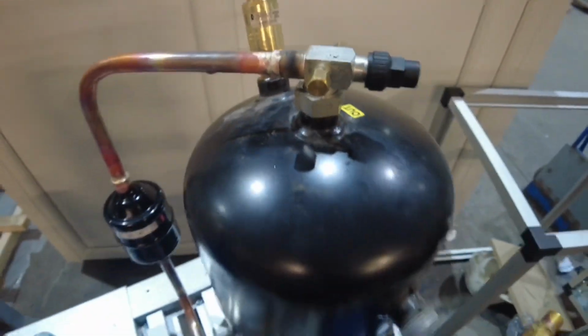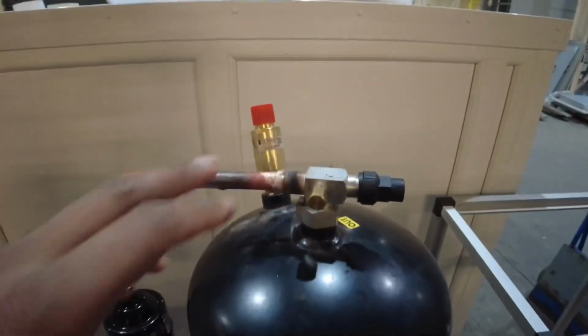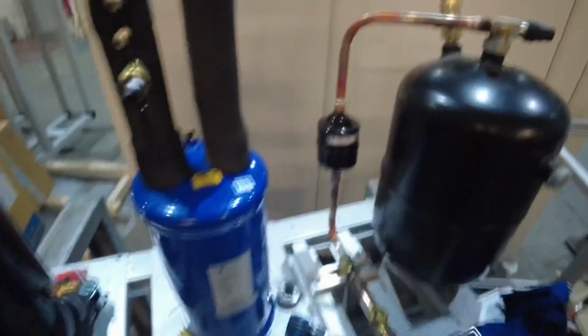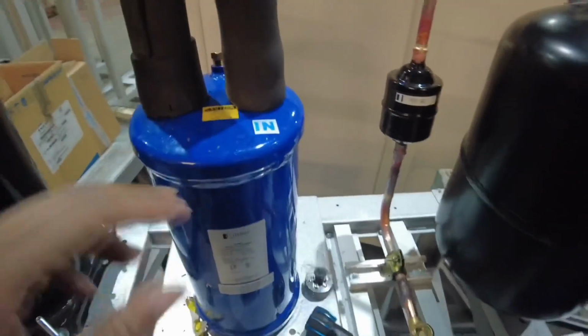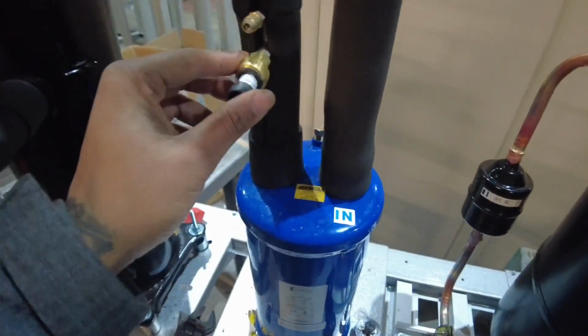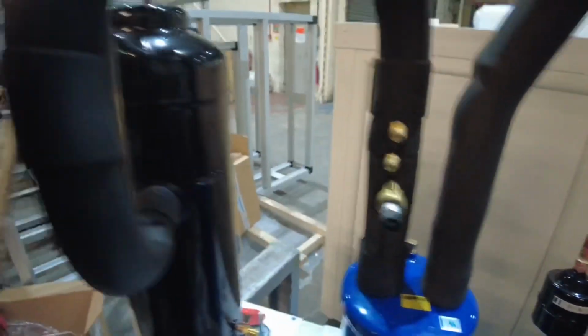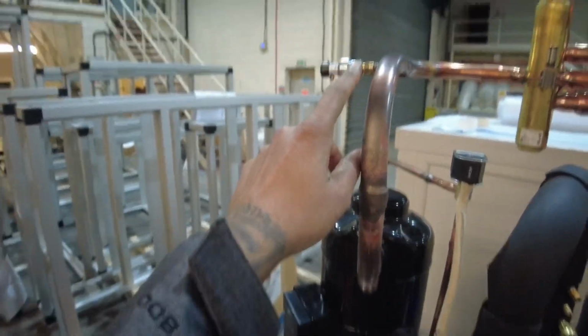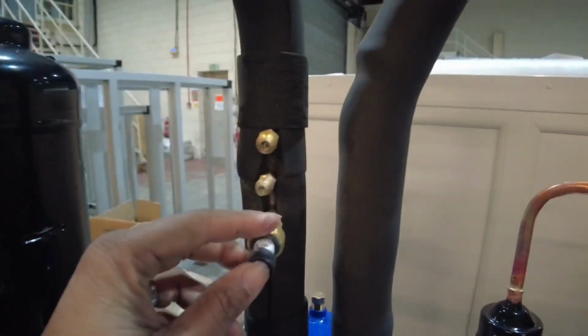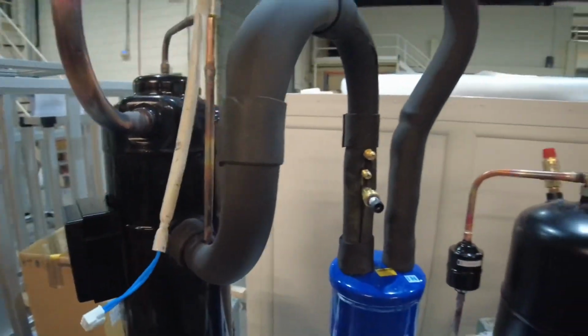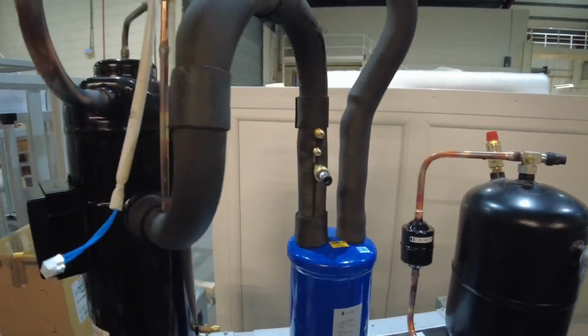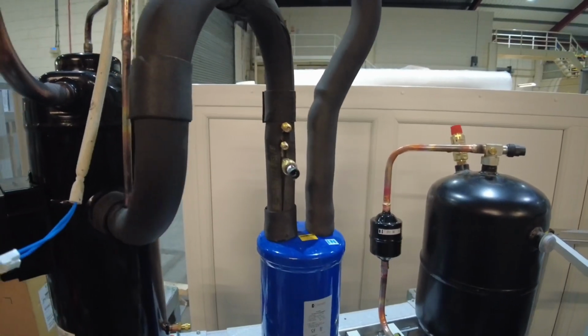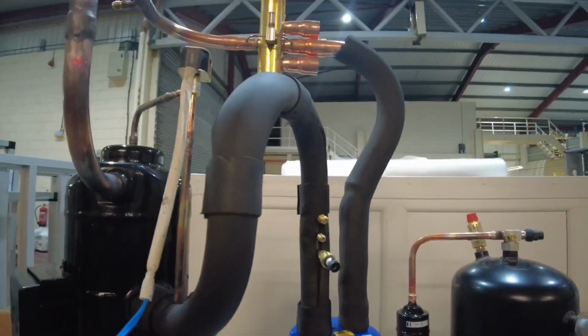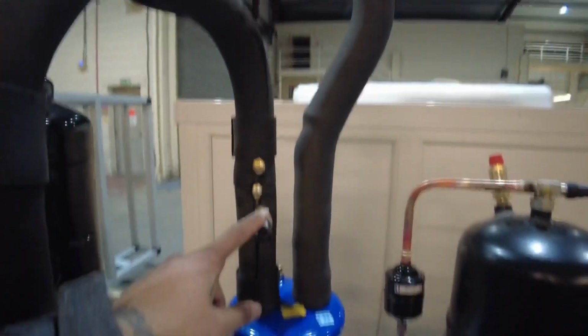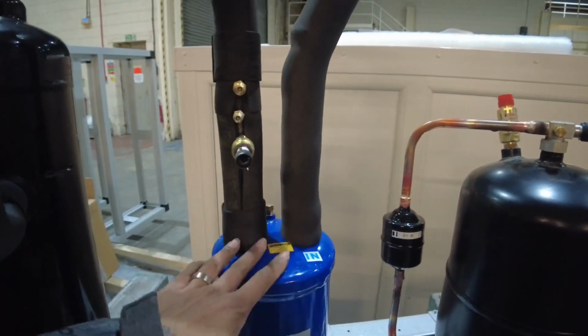If the pressure does get too high in the system, that is basically a safety feature. Then we've talked about the accumulator before. We've got an LP pressure transducer, and we've also got a HP pressure transducer up there. The purpose of this is because we're using a superheat controller, so basically this system will run about 10 degrees superheat on the suction, so that's how this is controlled by this transducer, as well as a temperature sensor which is additional, which I need to put on.